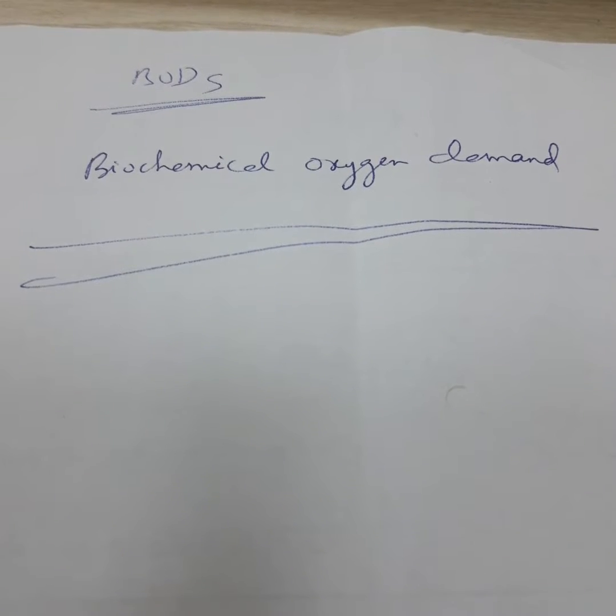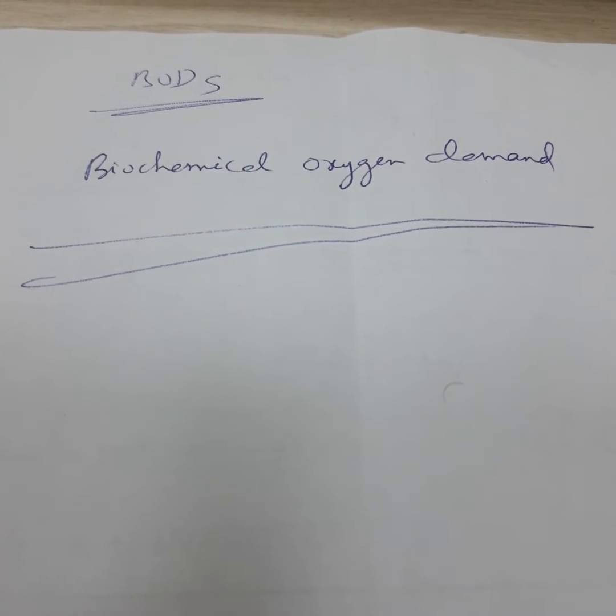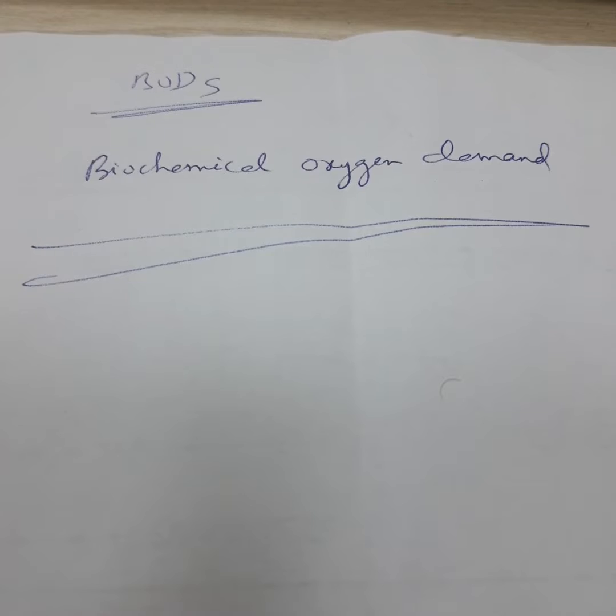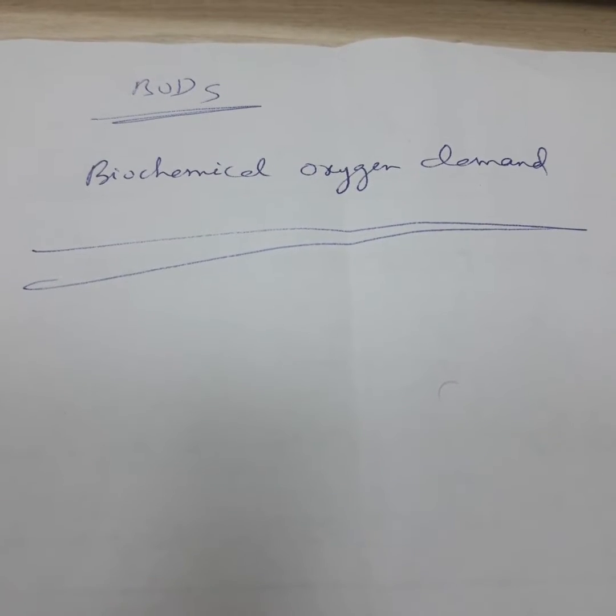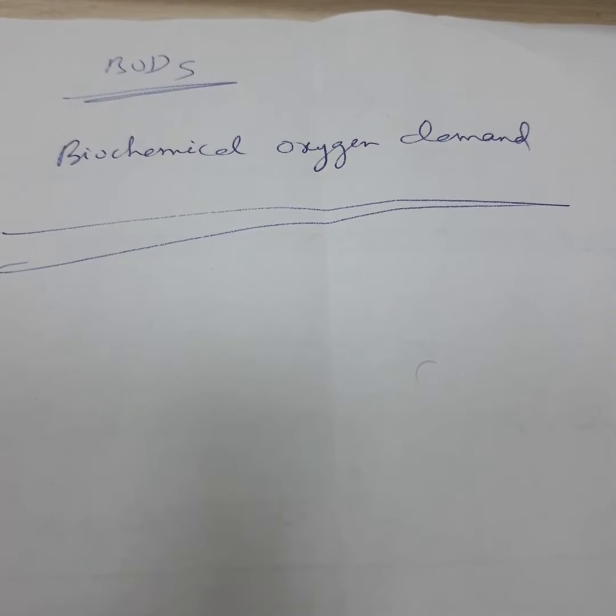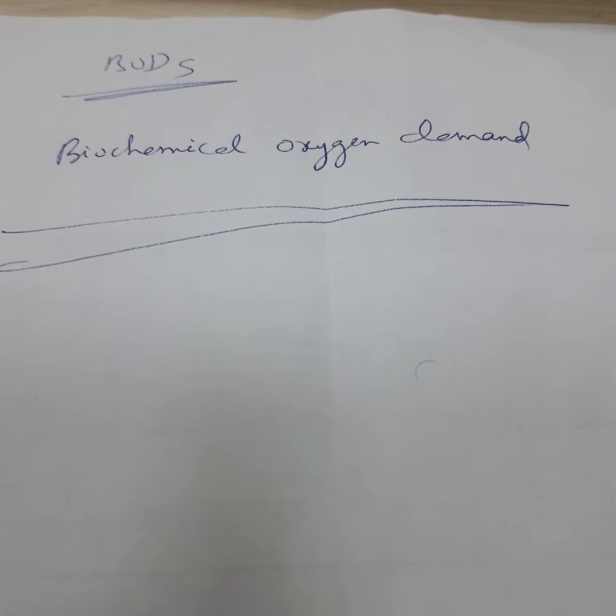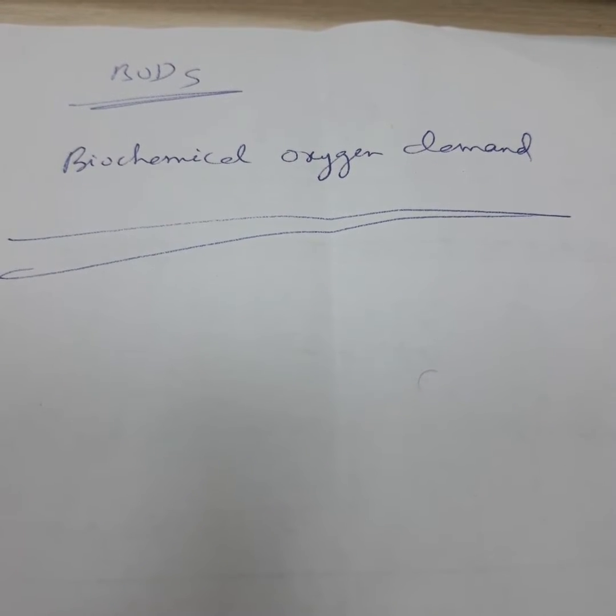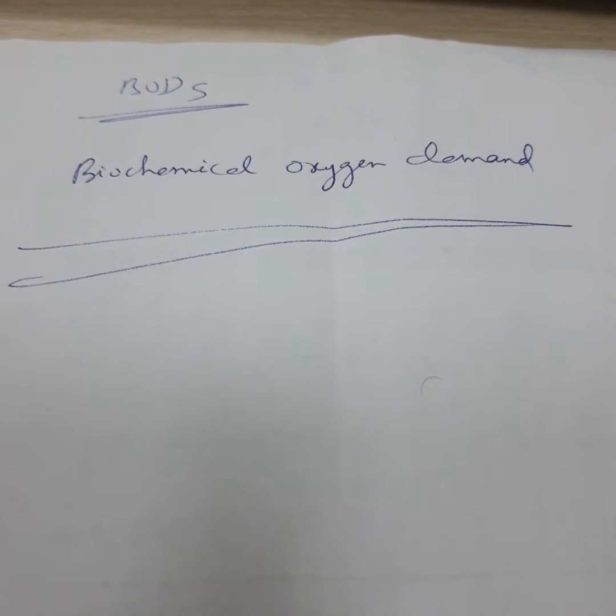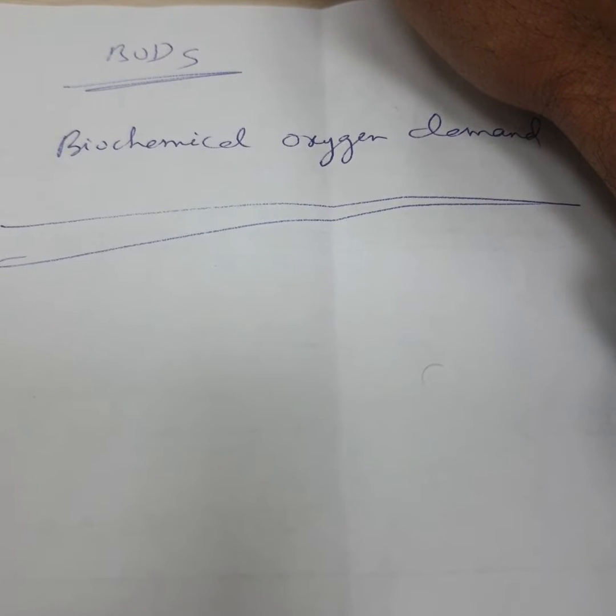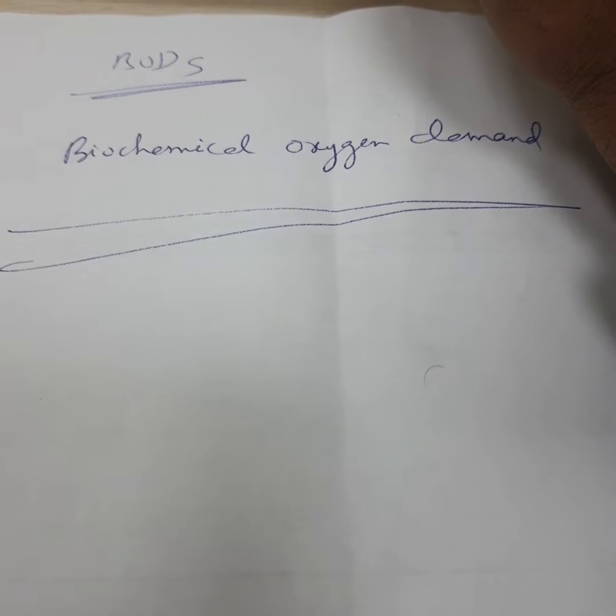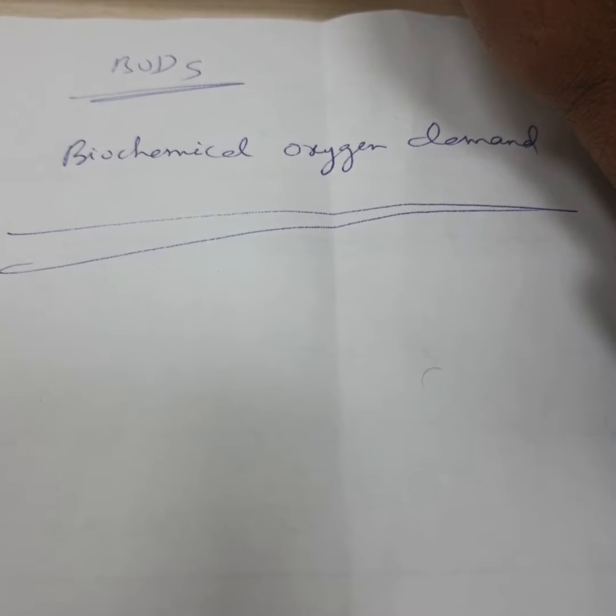BOD is part of the assessment of the quality of surface water and it enables us to understand the characteristics of dissolved oxygen in water and wastewater. Here we are going to use the device called OxyTop. The objective is to understand the meaning of BOD as a wastewater quality parameter and to use the OxyTop BOD measuring system. BOD is an indicator of the potential for a water body to become depleted in oxygen and possibly become anaerobic because of biodegradation.